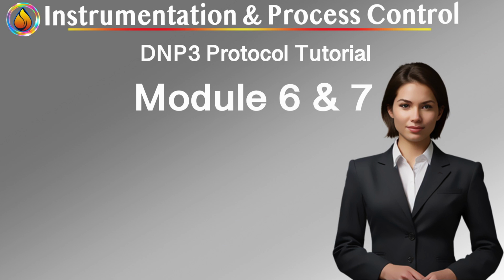7.12 End-to-end integrity model. DNP3 reliability is achieved through layered redundancy, not reliance on a single mechanism. CRC-based error detection, sequence control and duplicate rejection, fragment reassembly validation, explicit confirmations, buffered recovery mechanisms, embedded data quality flags. Together, these mechanisms ensure that data and control actions delivered through DNP3 remain accurate, auditable, and trustworthy, even in the presence of severe communication impairments.